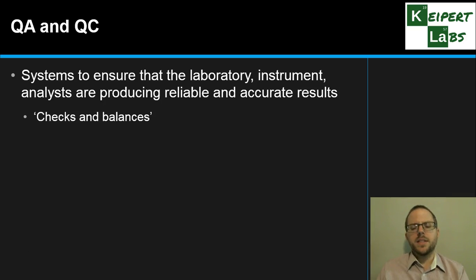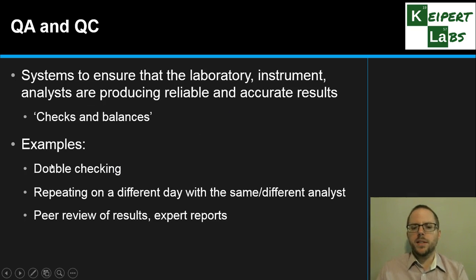And speaking of double checking, we get to our last main point talking about quality assurance and quality control. Probably the shorthand way you could understand that - quality assurance is what you do before you do the testing. Quality control is what you do to check after and during the testing. So QA is setting things up and QC is your monitoring basically. So it's the systems that we put in place to ensure that the lab, the instrument and the analysts are producing reliable and accurate results. Colloquially we might say they're the checks and balances. The things that we would do to make sure that things are working the way that they should, whether that's at the big picture, the level of the lab itself and its own systems, the instrument we're using and the people that are using it.